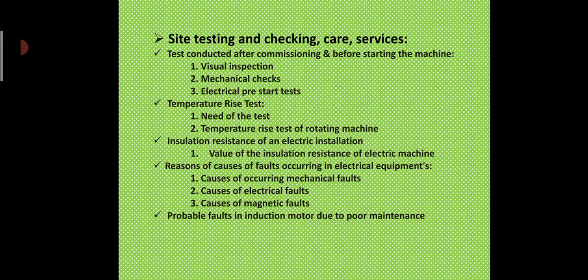If proper care is not taken about the belt and the belt becomes too tight, the load on the motor increases and the motor gets heated up. On the other hand, if the belt becomes loose, the belt slips and improper transmission of power results. Heat dissipation from the winding reduces and its temperature increases if dust and dirt are not removed periodically from the winding. Insulation resistance of the winding decreases. There is a probability of an earth fault if the varnishing of the winding is not done at the required time. Grooves are produced on the slip ring and sparking occurs if proper maintenance of slip rings and brushes is not done.